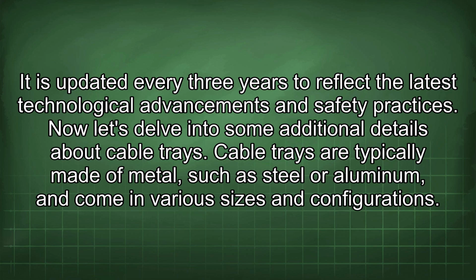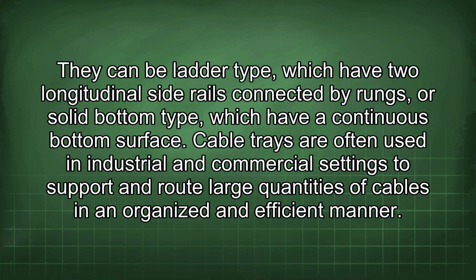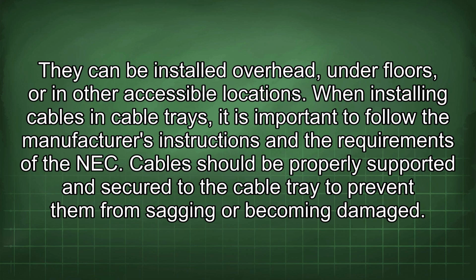Now let's delve into some additional details about cable trays. Cable trays are typically made of metal such as steel or aluminum, and come in various sizes and configurations. They can be ladder type, which have 2 longitudinal side rails connected by rungs, or solid bottom type, which have a continuous bottom surface. Cable trays are often used in industrial and commercial settings to support and route large quantities of cables in an organized and efficient manner. They can be installed overhead, under floors, or in other accessible locations.